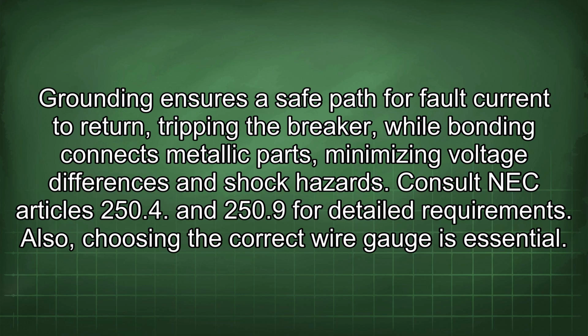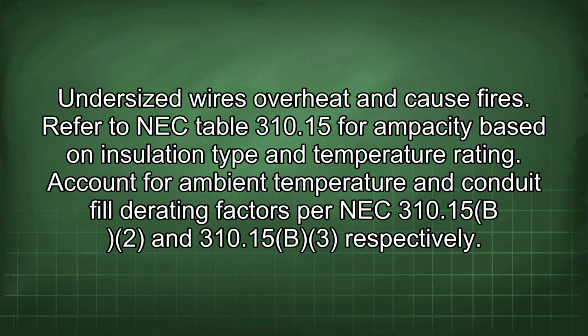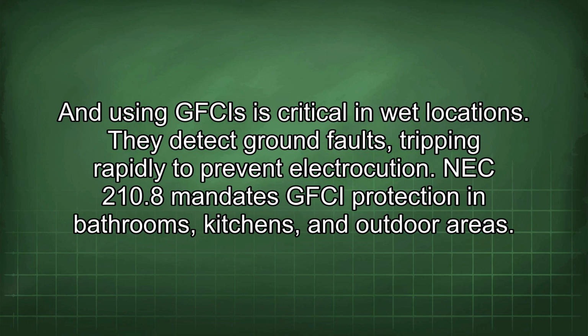Also, choosing the correct wire gauge is essential. Undersized wires overheat and cause fires. Refer to NEC Table 310.15 for ampacity based on insulation type and temperature rating. Account for ambient temperature and conduit fill adjustment factors per NEC 310.15(B)(2) and 310.15(B)(3) respectively.